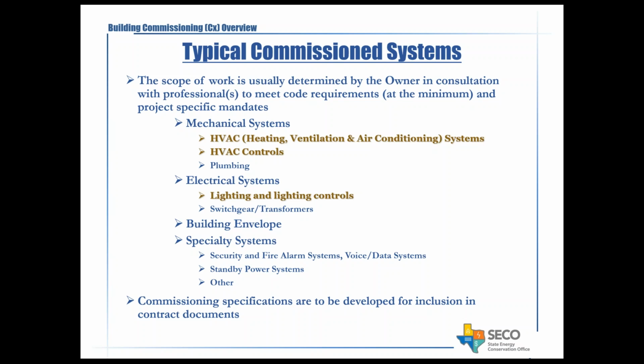As a result, commissioning became a popular tool to control that aspect and do a better job at it. One important thing is that the commissioning specifications will be developed by the commissioning engineer and included in the contract documents. You want to do that because the contractor needs to be aware that he has to allocate time and effort to work with the commissioning agent on testing and follow-up testing.